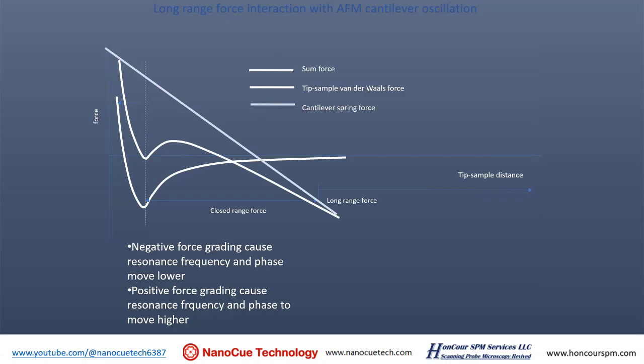A negative force gradient causes a resonant frequency shift, and a positive force gradient also causes a resonant frequency shift. Other than this short range force, there is also long range force. Here we overlap some long range force gradient — for example, magnetic force. The atomic force microscope tip will sense the force, whether it comes from a magnetic force, an electrical static force, or other sources. It is long range force: a force beyond 10 nanometers, all the way to a couple of microns.